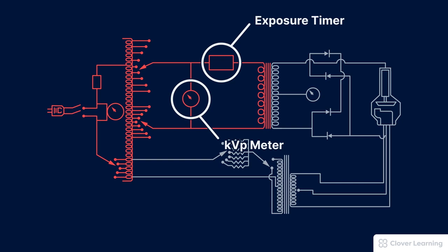The exposure timer is placed in the primary side of the circuit to control how long the exposure stays on. And this makes sense. Since the primary circuit controls the kVP, it makes sense that the exposure timer needs to be in the primary circuit.